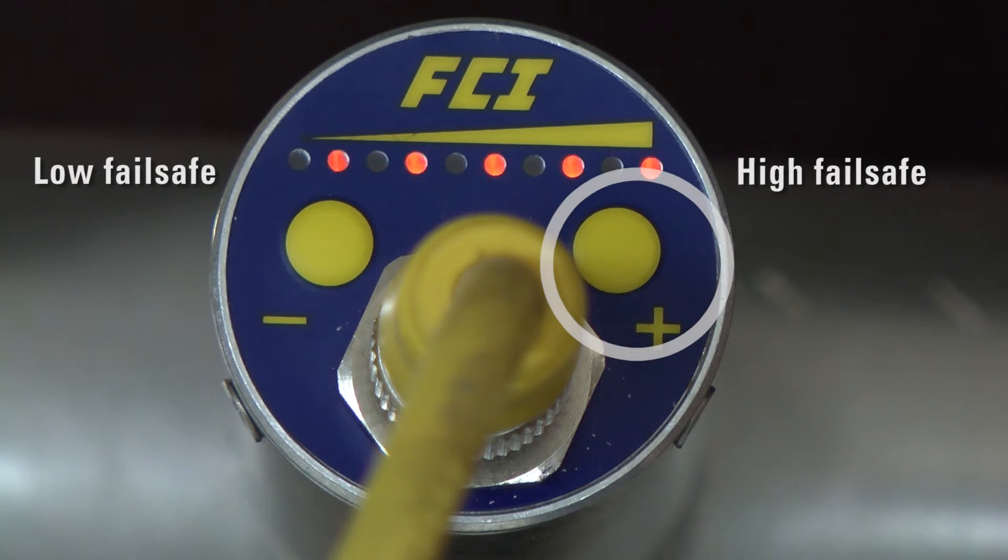Now momentarily press the minus button to exit with a fail safe low—that is, relay is de-energized in the alarm state—or the plus button for fail safe high—that is, relay de-energized above the setpoint.